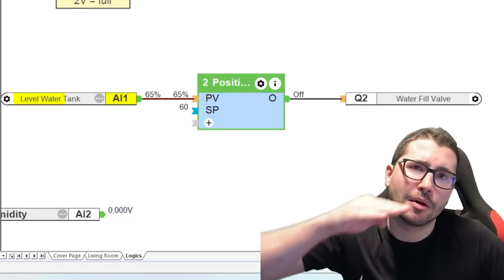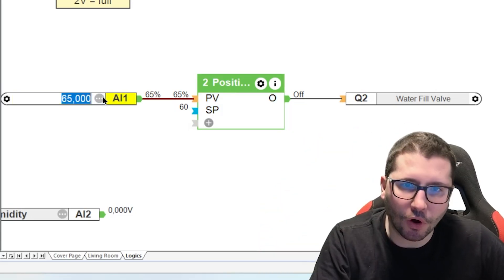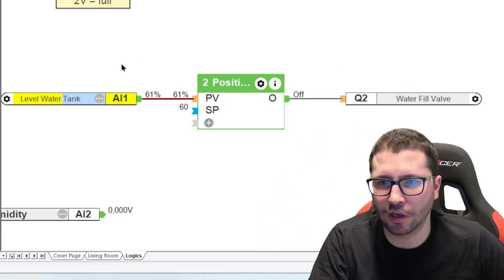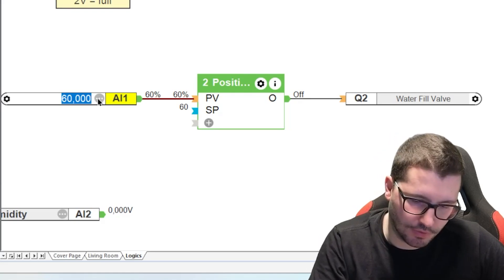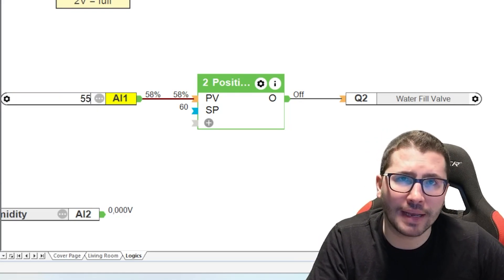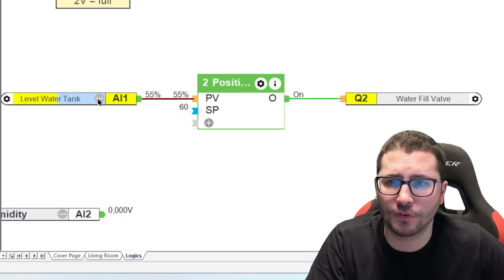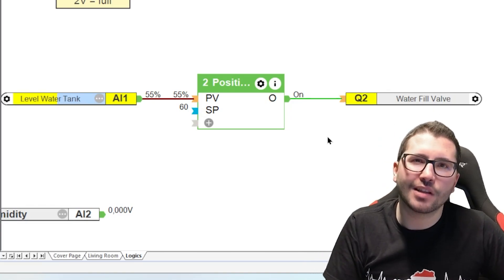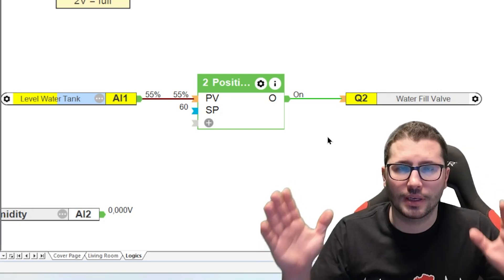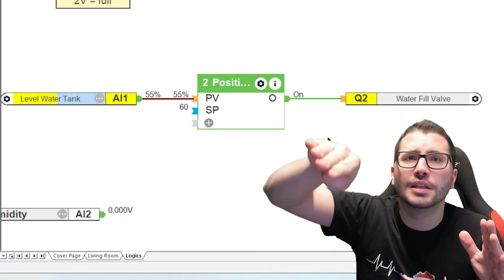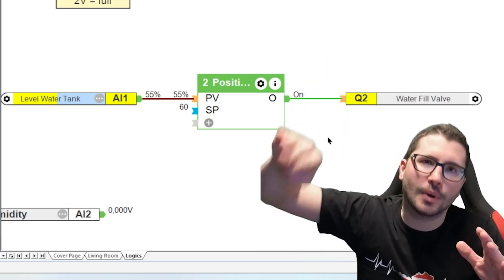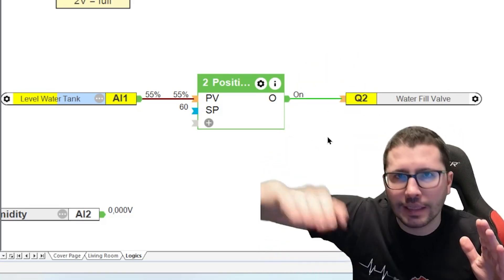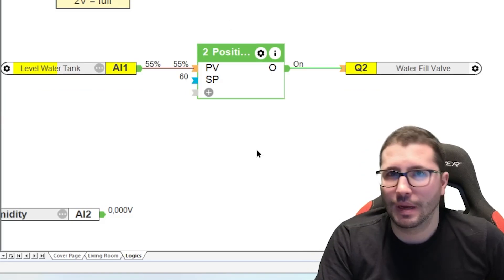65 and it stops. And that's exactly our hysteresis. It's plus minus what we type in here. What if we fall? 61. Still off. 60. Still off. 58. Still off. Until we reach 60 minus our hysteresis. So 55. Then it starts again. And with this logic, it's like in the fridge. It starts the compressor, it's cooling down two degrees, and then it waits until there is a two degree increase again, and then it starts again. Otherwise, the compressor would permanently restart like we had before with the less function block.